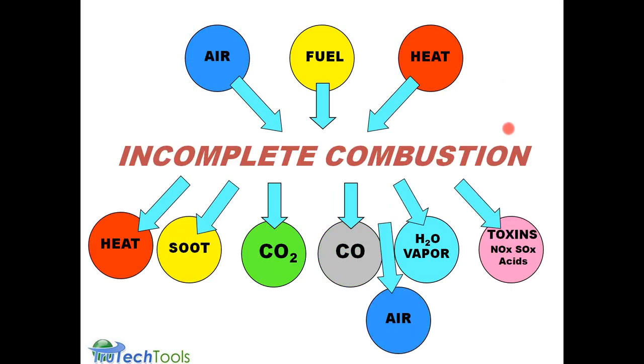In most cases, in the real world, you have at least some incomplete combustion going on. And when you have incomplete combustion, you have products that weren't in the last slide that are produced. Those products are things like soot, which would be mainly visible in an oil burner system, oil heating, but it's even visible to some degree, with a very fine microscope, in a natural gas system. You have carbon monoxide, this gray balloon.